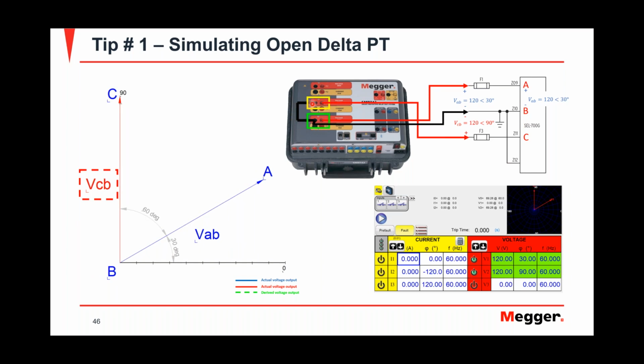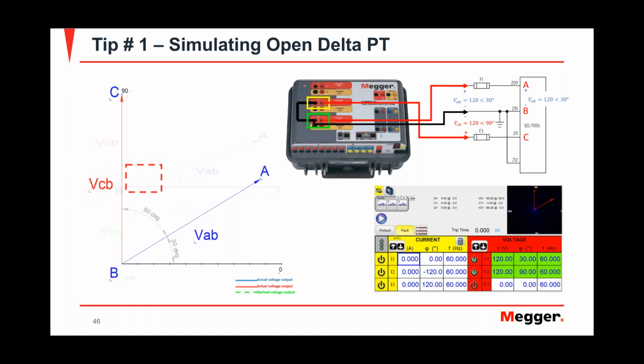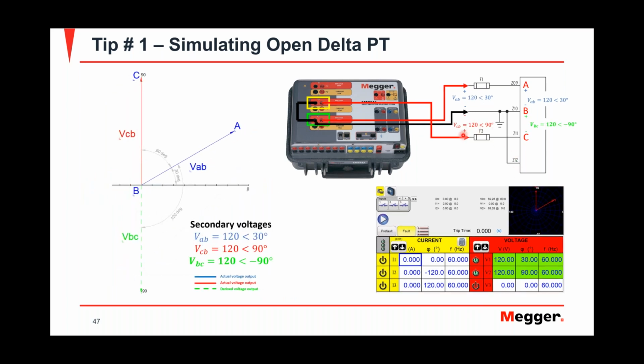So both the B phase on the second channel, your black terminals, you put a jumper in there, and you inject a C to B voltage into the relay. And that would be 120 at 90 degrees. So if you're an electrical engineer, your phasor will look like this. It's 90 degrees up. But bear in mind, this is your voltage C to B, and the relay wants to see B to C. So now you're injecting voltage C to B, 120 at 90, but your relay is going to interpret it as 120 minus 90, because that's how the relay sees it.